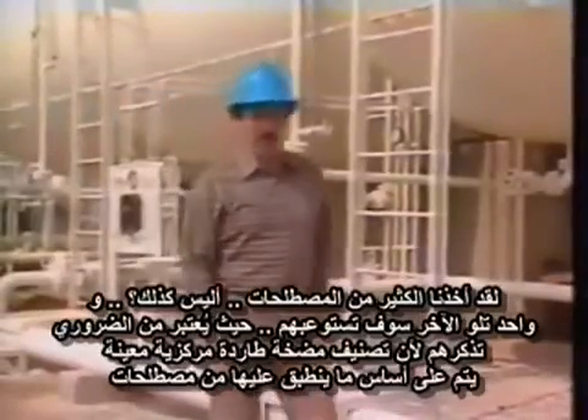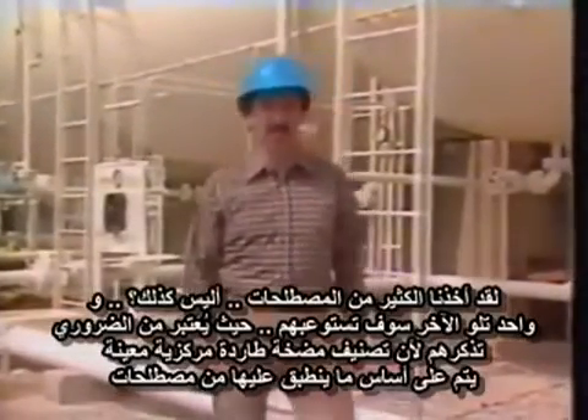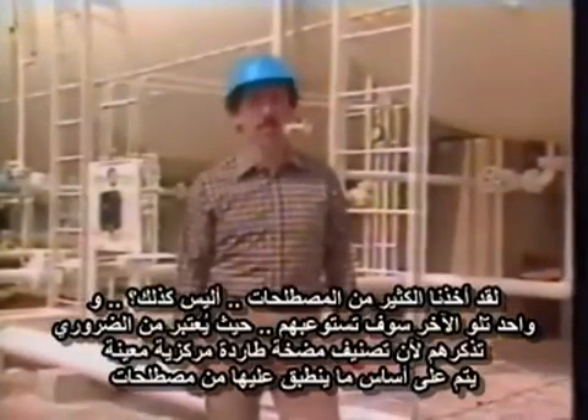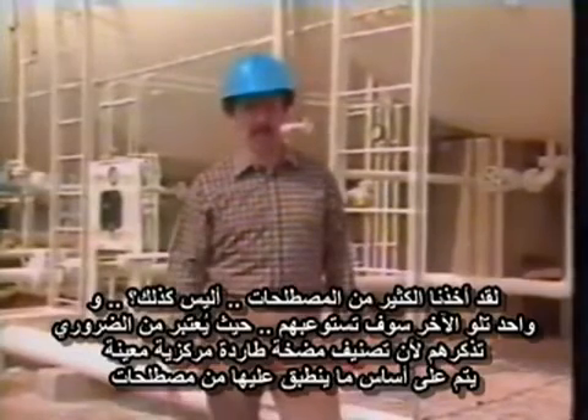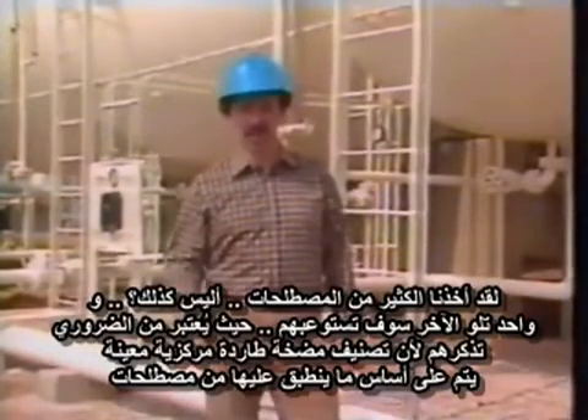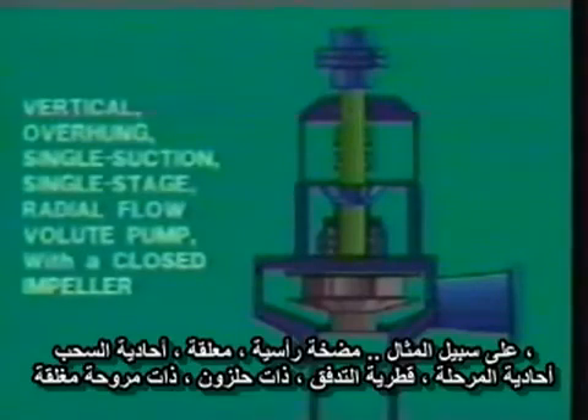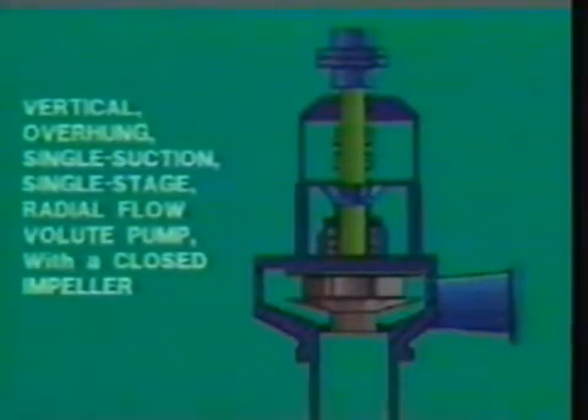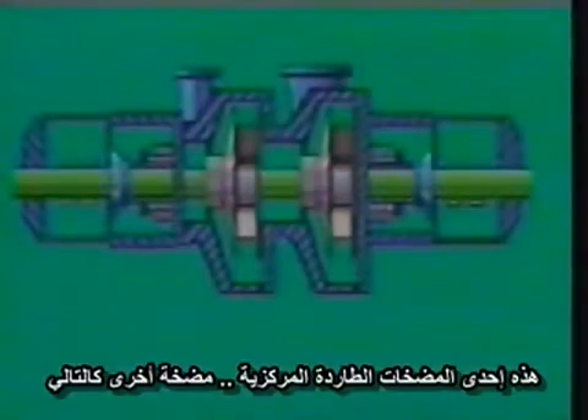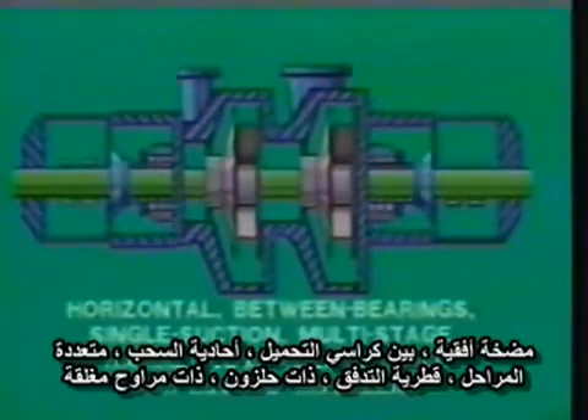We've got a lot of terms, right? And one by one, we can understand each. That's important to remember because a specific centrifugal pump is classified by which terms are applied to it. For example, a vertical overhung single suction, single stage radial flow volute pump with a closed impeller. That's one centrifugal pump. Another one is this one: a horizontal between bearings, single suction multi-stage radial flow volute pump with closed impellers.